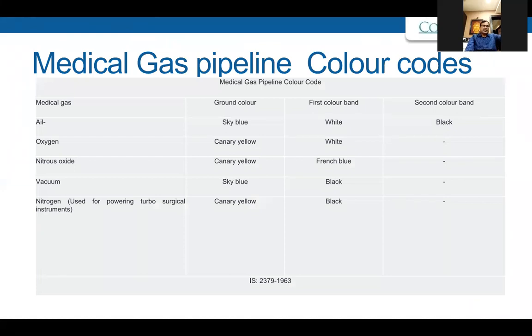Yeah. So there is a lot of confusion about medical gas pipeline color coding. I would like to reiterate here that you can put HTM color coding or NFPA color coding or ISO color coding, which is mentioned in your slide, this is an IS color coding, but you can follow HTM, but it should be consistent. It should not happen that in one place you are following IS, in another place you are following HTM because your vendor changed, and there is no marking of direction of airflow.